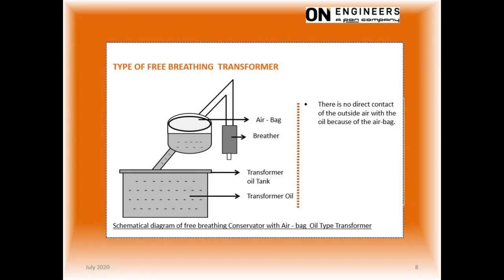This slide shows a variant of the breathing type transformer. The silica gel breather has limitations to remove moisture from the outside air. Once the silica gel is saturated with moisture, it will not prevent further contamination of the oil with moisture. The solution is to install an airbag in the headspace of the conservator tank. In this way, the oil will never be in contact with the outside air.